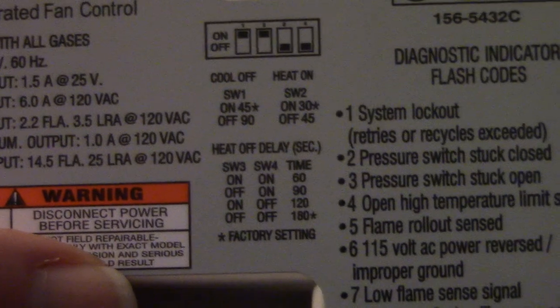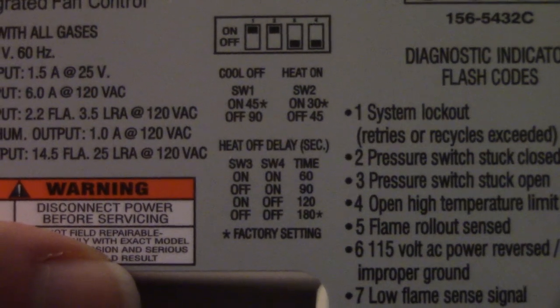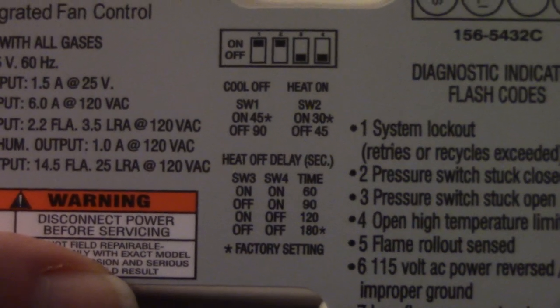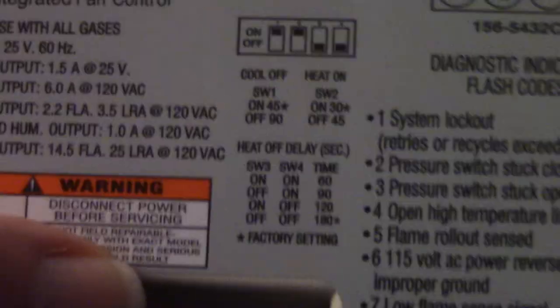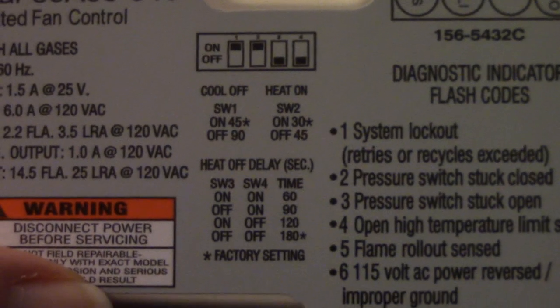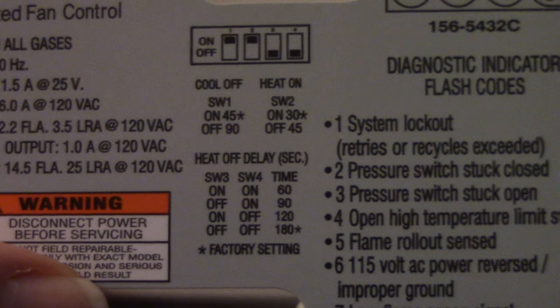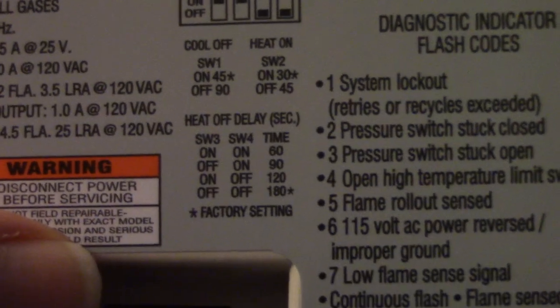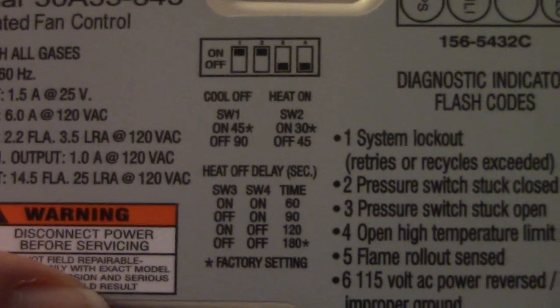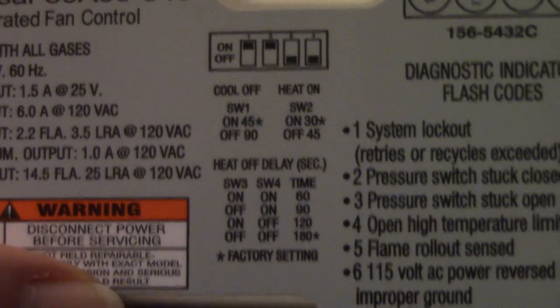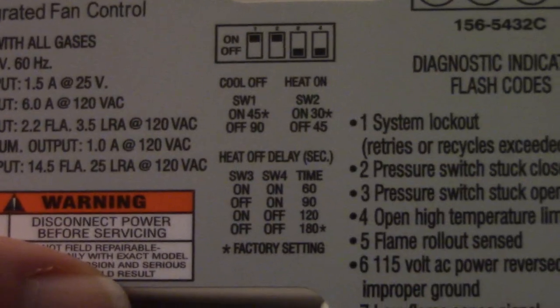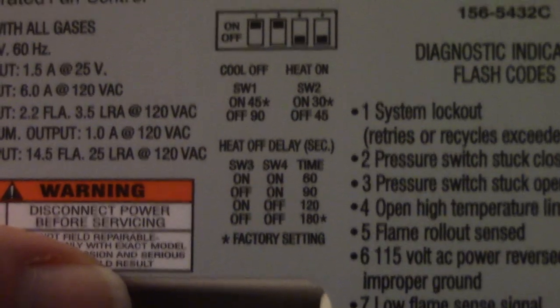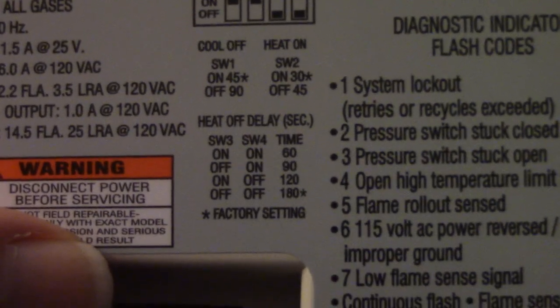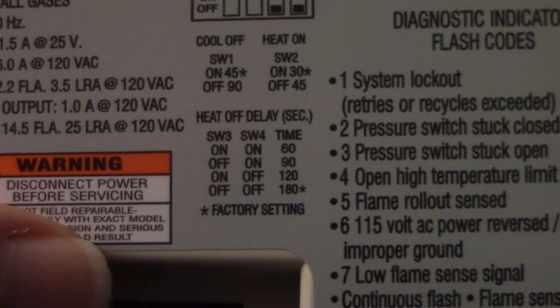It's one of those where you spend money on the gas to heat up the heat exchanger to replace the heat that the house lost. So how long do you want to run afterwards? Me personally, I'll run it at the 180. Yeah, it does put a little bit of chilly air there, but I like having the extra circulation to balance the air in the house out. Some people don't like that cold air, and it is adjustable to reduce it.